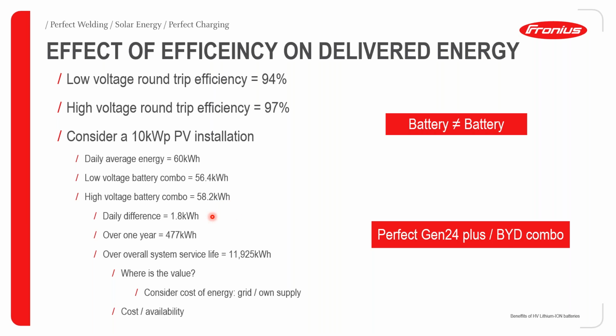So on a daily basis, there's a difference in energy delivered of about 1.8 kilowatt hours. Extrapolating this over a period of 1 year, we're talking about a difference between the low voltage and high voltage configurations of about 477 kilowatt hours. Looking at a service lifespan of about 25 years for this system, the difference in energy delivered becomes quite huge.